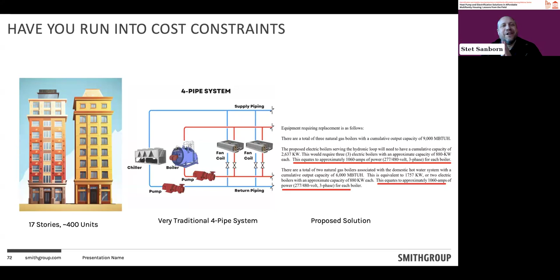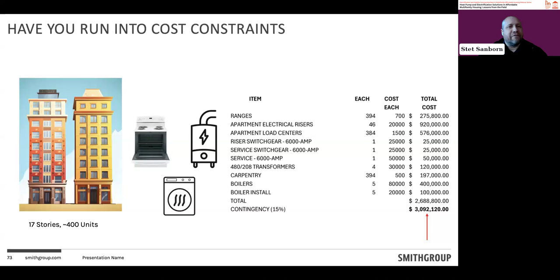The other challenge was when they looked at tracing all that electrical service up into the unit. So electric range, electric space heating, electric dryer instead of all the gas. With that 60 amp service, they were going to have to upgrade all the risers up through the entire building, which is a huge undertaking. When the cost estimate came back, you'll notice that the total cost for this project, just to do that in-unit work and the space heating, was going to be about $3 million, of which 2/3 was just the electrical infrastructure upgrades. So when we make decisions, we want to change the approach to our project to bring in our strategies within the electrical constraints that we have for the project. Next slide.